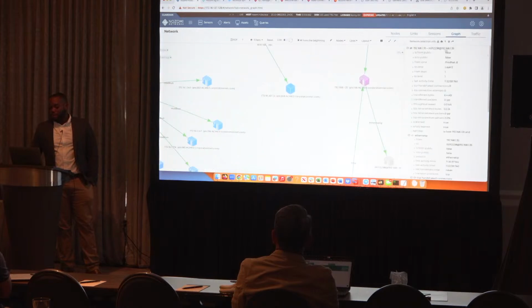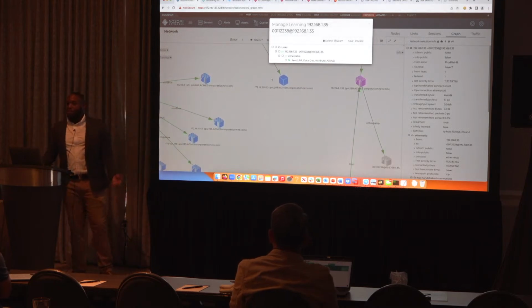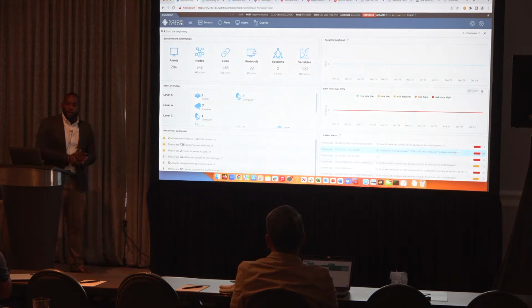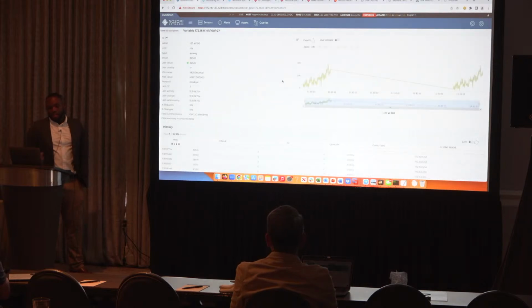And then how that works with the learning of it, from an Ethernet IP communication, these are the function codes that we've seen and what gets learned and unlearned. And then even if we go another level deeper, to the field process level, the I/O analog digital connections, we call them variables. We can even get down to that level to say, this PLC has X amount of I/O points, analog digital connections. What are we doing with that? We're looking at those to see if there are any deviations or anomalies there as well. So if you think of the different verticals, speeds of belts, fans, levels in tanks, batteries discharging, recharging, et cetera, they usually have a consistent cycle or pattern of life, as people call it, right? So if that changes, we are documenting the minimum, the maximum, all the values in between.